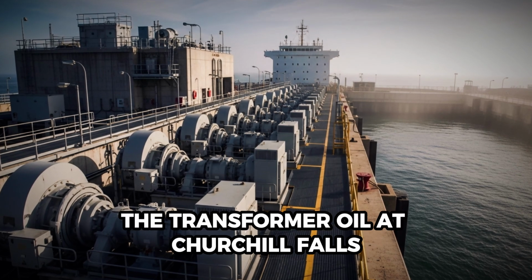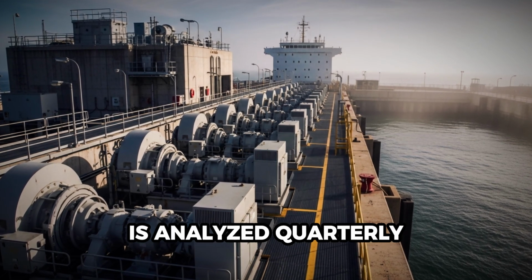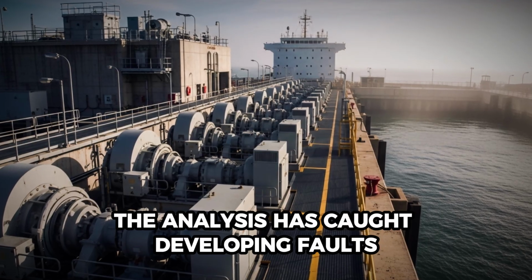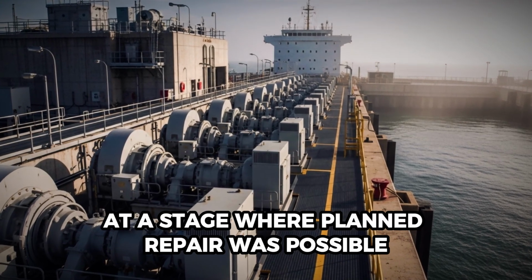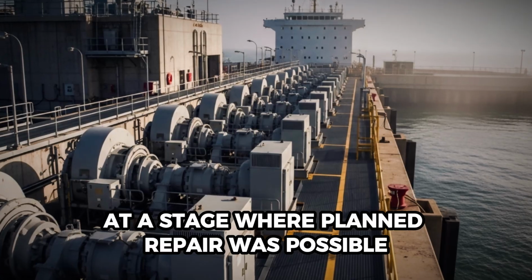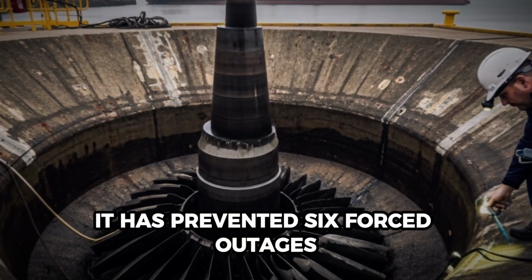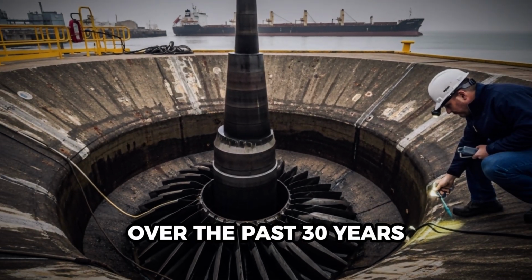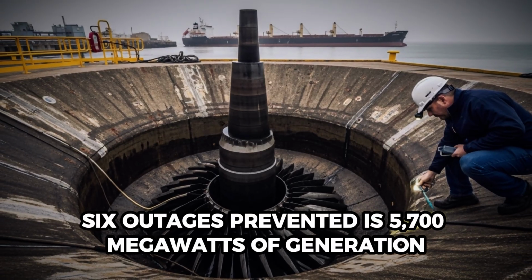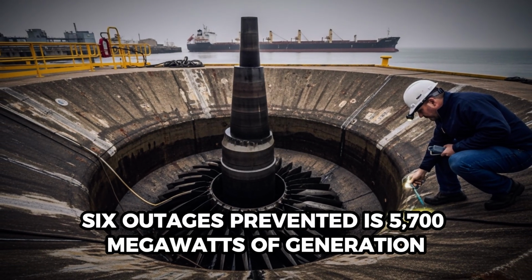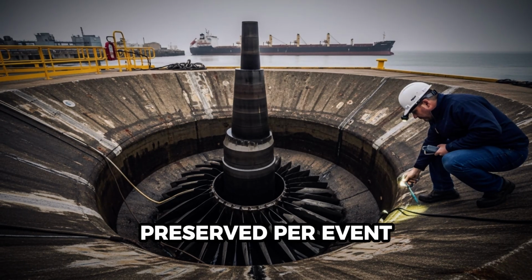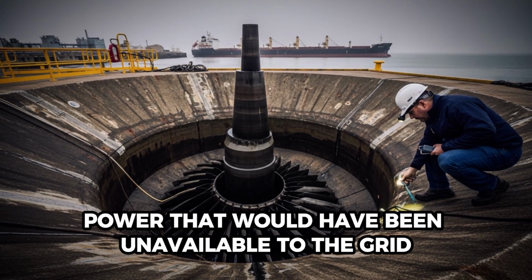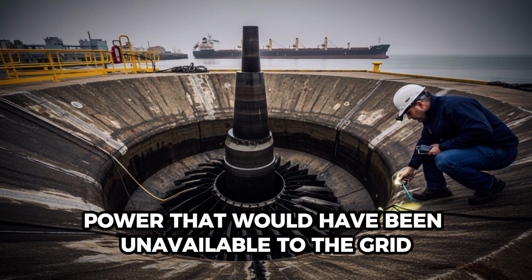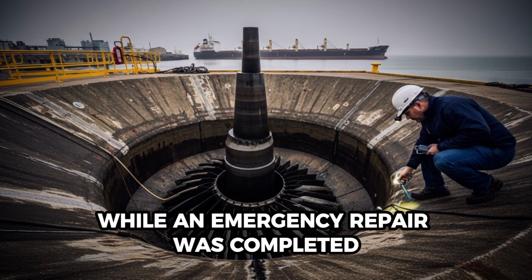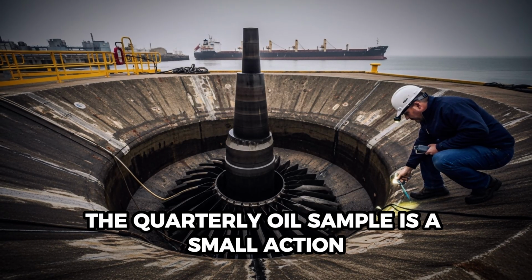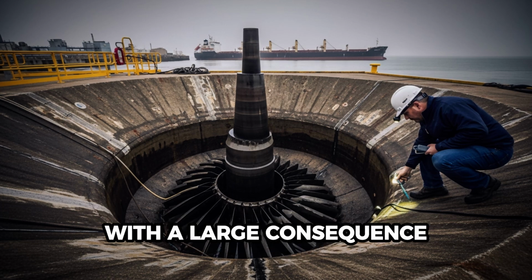The ratios of these gases in the oil tell a trained analyst which fault type is developing and how severe it is. The transformer oil at Churchill Falls is analyzed quarterly. The analysis has caught developing faults at a stage where planned repair was possible. It has prevented 6 forced outages over the past 30 years. 6 outages prevented is 5,700 megawatts of generation preserved per event. Power that would have been unavailable to the grid while an emergency repair was completed. The quarterly oil sample is a small action with a large consequence.